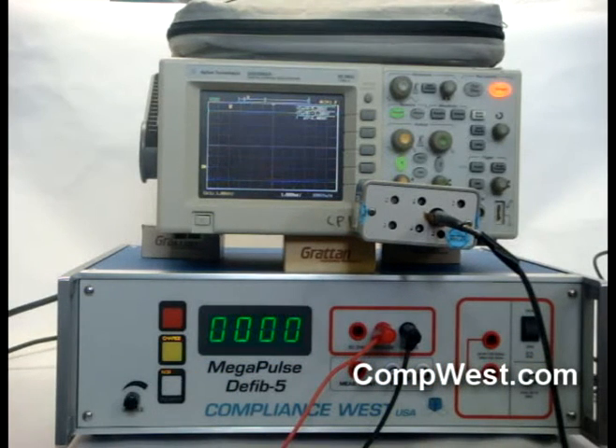Two tests are conducted, one with the device under test connected to the output of the Defib-5 and one with no connections to the output of the Defib-5. The energy delivered to the 100 ohm load with the device under test connected must be within 10% of the energy delivered with nothing connected to the Defib-5.